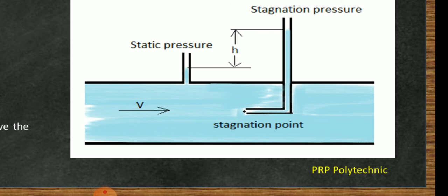The fluid flowing through the pipe passes through the pitot tube horizontal section, causing a stagnation point, which creates stagnation pressure. Due to stagnation pressure, the height of the fluid will rise into the vertical tube. This height will be measured and used in the flow measurement formula. This is how you can calculate flow measurement using pitot tube, orifice meter, and venturimeter.